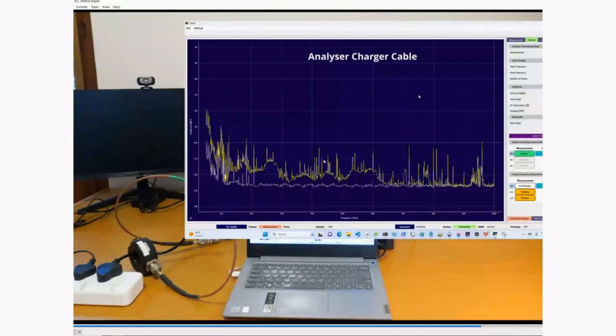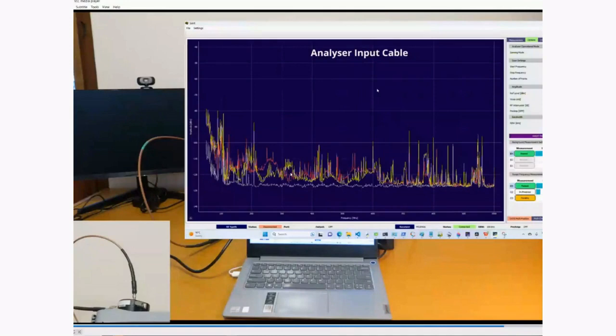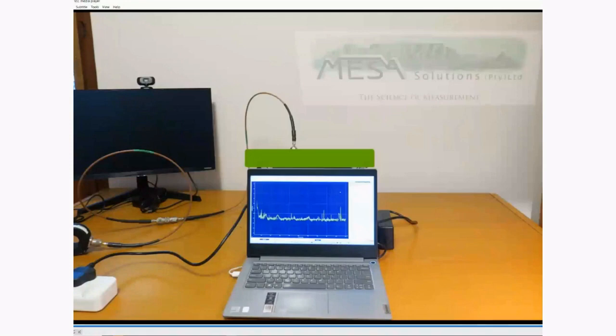I'll let you just look at this. This is on maximum hold. We then connect it to the input of the spectrum analyzer, and we see very similar high levels of energy right on the outside of the coaxial cable entering our spectrum analyzer. And let's record that. You can see quite a noisy picture. And then finally, we're going to look at the energy on the screen power cable, and you'll see that's in the yellow trace now, much, much lower. It picks up the environmental cell phone and FM, but also picks up a little bit of the noise from the spectrum analyzer. Now that's what happens if you do not use an EMC cabinet.